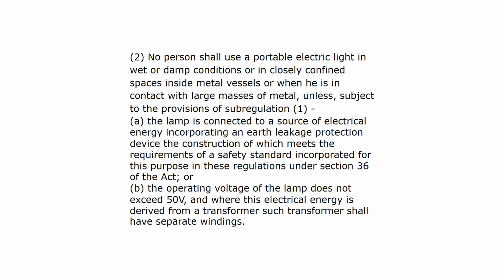No person shall use a portable electric light in wet or damp conditions, or in closely confined spaces inside metal vessels, or when he is in contact with large masses of metal, unless subject to the provisions of Subregulation 1. The lamp is connected to a source of electrical energy, incorporating an earth leakage protection device, the construction of which meets the requirements of a safety standard incorporated for this purpose in these regulations under Section 36 of the Act, or the operating voltage of the lamp does not exceed 50 volts, and where this electrical energy is derived from a transformer, such transformer shall have separate windings.